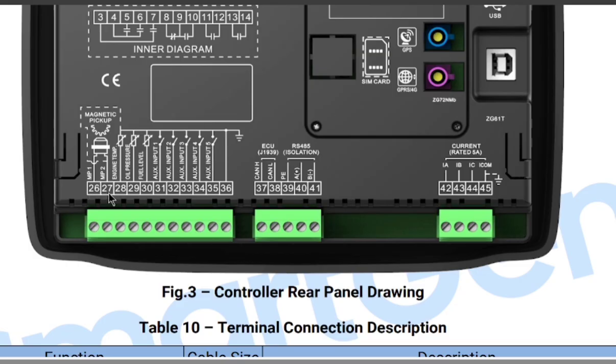As you can see here, the MPU, magnetic pickup unit, you should input the 2 wires here, and after that the engine temperature sensor input, the oil pressure sensor input, the fuel level sensor input, and the auxiliary input. Here we have some auxiliary inputs, which means you can use them for any general purpose. Like if some engines have more sensors, you should use these auxiliary inputs, and you only need to program them in this controller through the software.